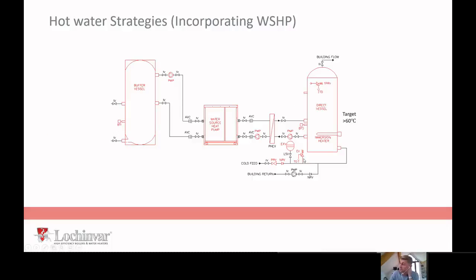But by far our most popular schematic at the moment is definitely this one, shopping centres, whatever it may be. We have a thermal store, which will be at 35 degrees, typically served from an ambient loop. And that ambient loop will be a big one in a building, probably in a multi-functional style build. The water source heat pump can then pick up that 45 or 35 degrees, which is flowing around the building, go into a hot water system and turn it into a usable hot water application. Now, this is a really powerful tool because it allows you to tee into so many different things.